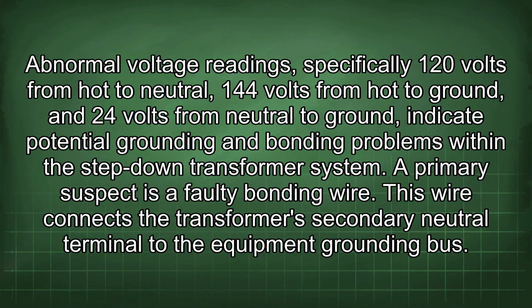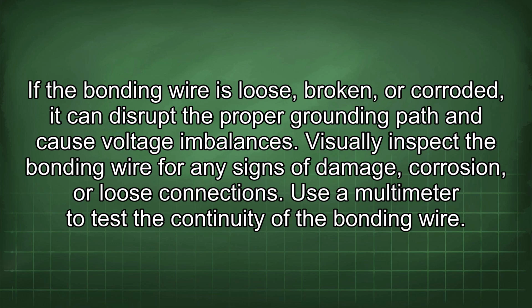Abnormal voltage readings, specifically 120 volts from hot to neutral, 144 volts from hot to ground, and 24 volts from neutral to ground, indicate potential grounding and bonding problems within the step-down transformer system. A primary suspect is a faulty bonding wire. This wire connects the transformer's secondary neutral terminal to the equipment grounding bus. If the bonding wire is loose, broken, or corroded, it can disrupt the proper grounding path and cause voltage imbalances.